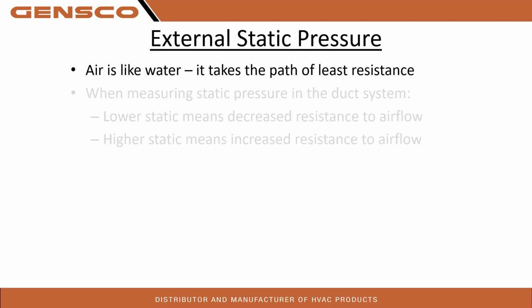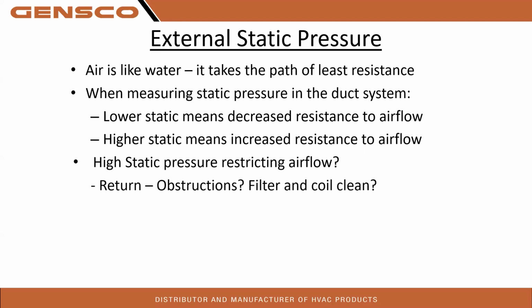When measuring static pressure in the duct system, lower static means decreased resistance to airflow. In turn, you will get more air. Higher static means increased resistance to airflow. So we'll have a higher static, higher amperage, higher amp draw on that blower motor, possibly leading to what? More heat and premature failure. So high static pressure restricts airflow.